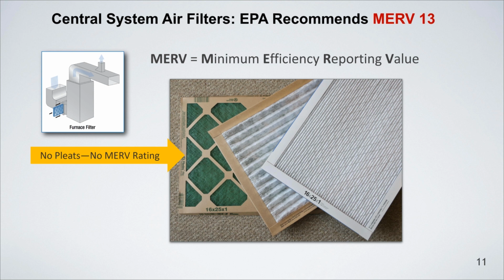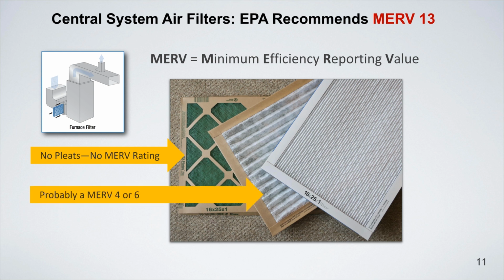Looking at those photographs, you can see how you move from not very much filtration to a lot of filtration—it has to do with the amount of fabric, the amount of filter paper in the filter. The green filter on the left is basically a polyester mesh; if you put your hand behind it, you'd still be able to see your hand. It's very good for protecting equipment—keeping hair, feathers, dust bunnies and the like from clogging your HVAC system—but it doesn't do much to protect people. It does a great job protecting the equipment and system from particles causing problems or residue in the ductwork.